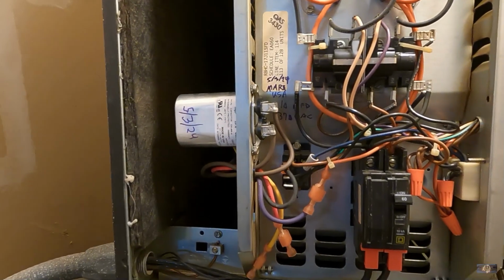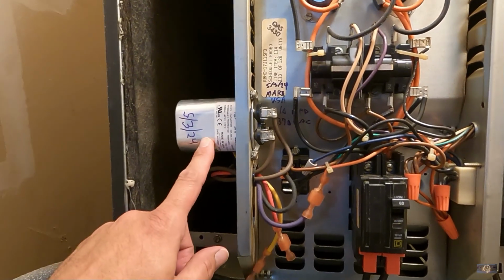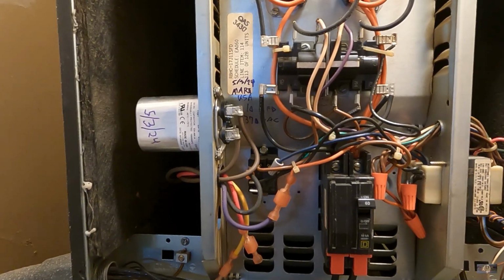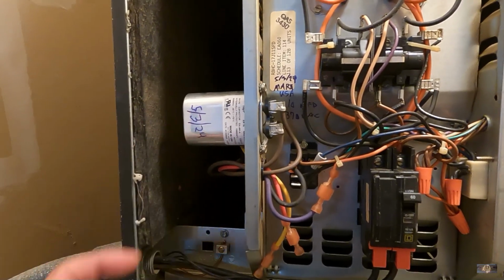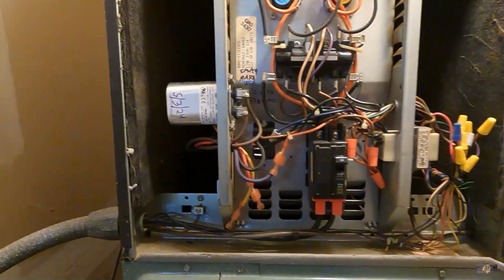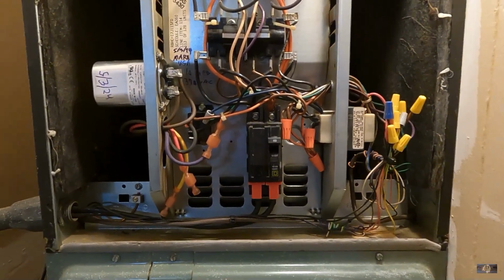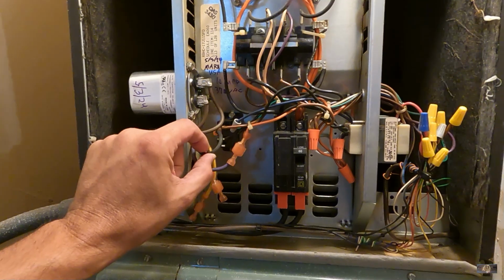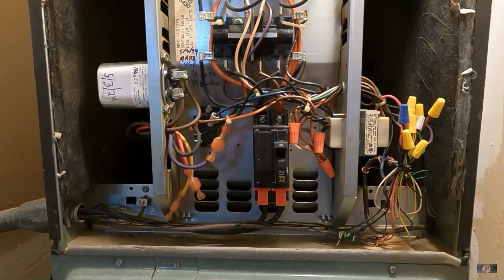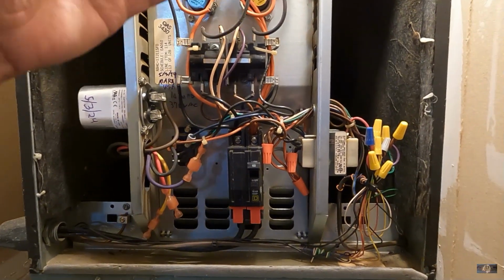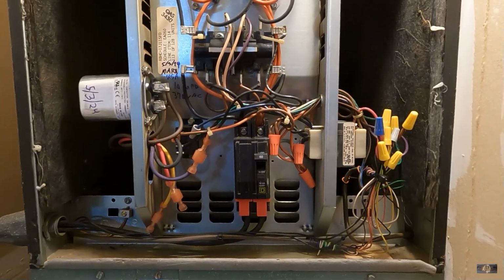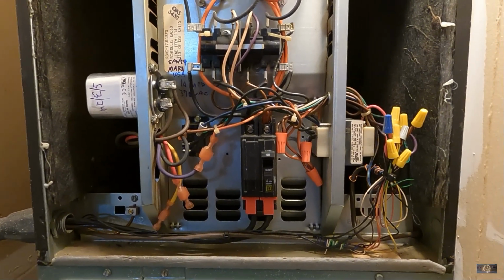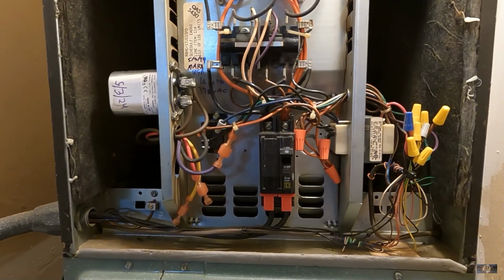I checked it, tested at 10 microfarads, but looks like I just did it in May of 2024. You gotta love the handwriting there, sideways, that's high quality. But yeah, that tested good. Fan speed is in high, which it definitely needs to be. This unit is way too big for the ductwork, and with the static pressure, the PSC motor actually slowed down.